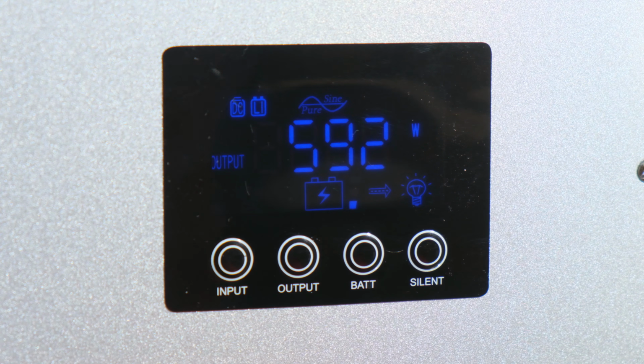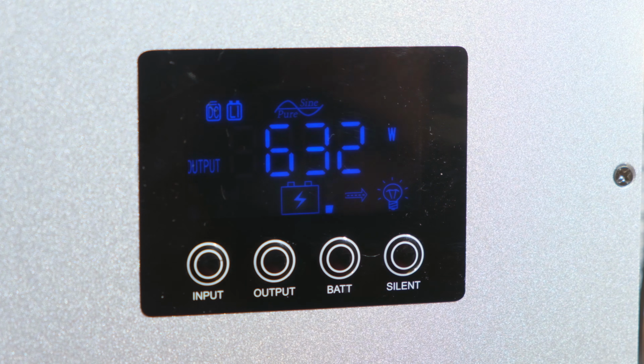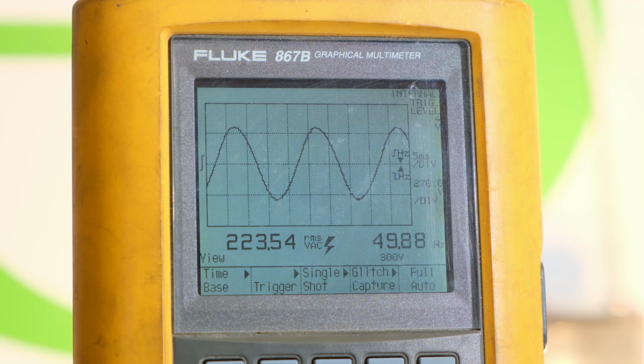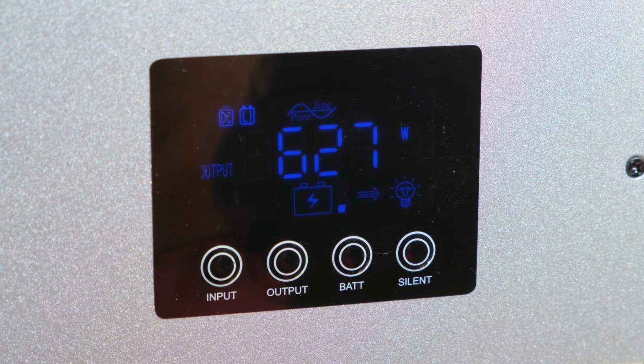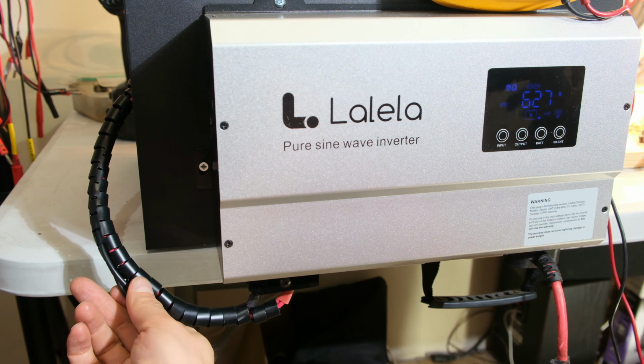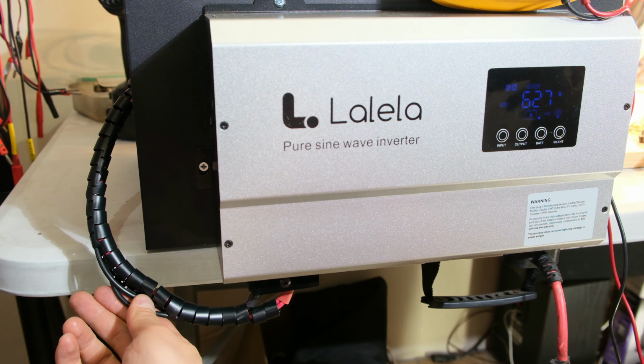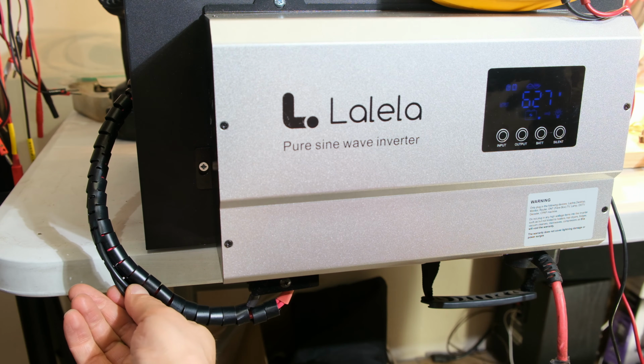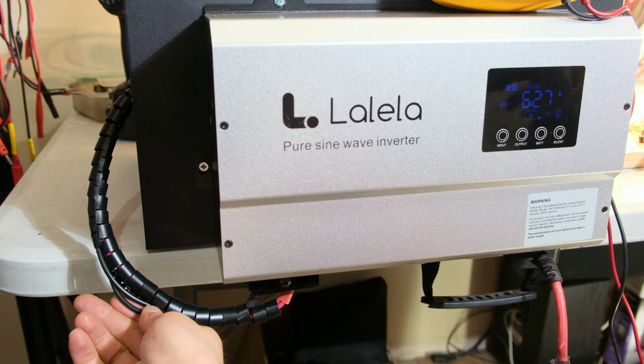Right, I'm now going to load it beyond 600 watts. Right, so now I've overloaded the unit. I can hear the buzzer is buzzing frequently now. It's telling me that there is definitely an overload on the unit, and let's see what it does. The output waveform is still good, even though I'm overloading it, and the frequency is pretty much 50 Hertz, and the voltage is 223 volts. So it's actually handling this overload condition very well. However, I noticed this wire from the battery side is pretty warm. And this heat was actually quite warm already from the 70% loading.